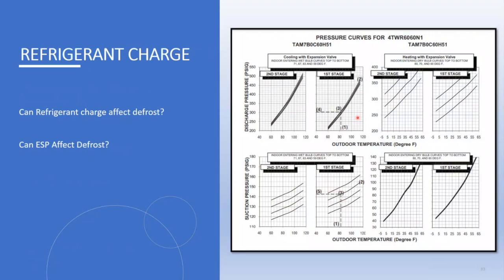So we talked about low charge. How do you verify charge? Well, the only way that we recommend to verify and adjust charge is by subcool if you have a TX valve in your indoor unit, or by superheat if you have a piston in your indoor unit. It has to be above 55 Fahrenheit outside, and your indoor temperature has to be between 70 and 80 Fahrenheit. But if you're seeing frost issues, it's probably not above 55 Fahrenheit.